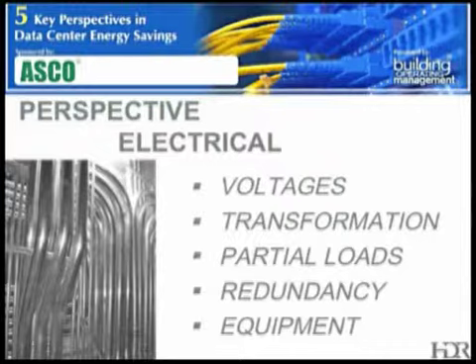end distribution. When we look at the transformation levels, typically we're seeing 7% of the losses in the UPS and maybe 2% in the PDUs. So when we design our systems, what we look to do is specify premium efficiency transformers to help reduce some of those losses. And it's important to remember when you're talking about transformers that those losses are going to be with you for the life of your system. So those need to be looked at and carefully considered. The money you spend there is going to be paying you back for the life of your transformer.